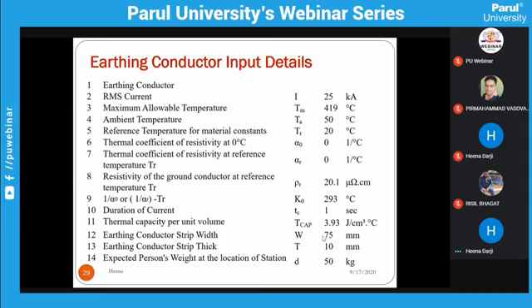This is the material property, means whether you are using copper or GI. It depends on your soil resistivity. So these are your properties: earthing conductor, your kiloampere, your RMS current, maximum allowable temperature, ambient temperature. These all depend on which conductor you are using for this earthing system.